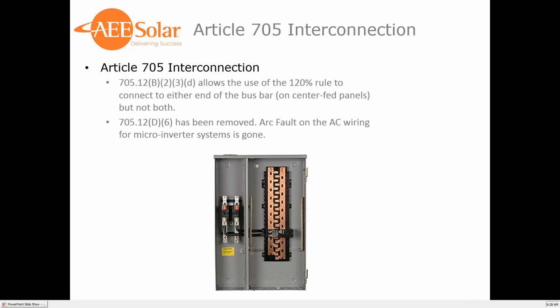So Article 705, interconnection. One of the biggest changes is to center-fed panels. 705.12B23D allows the use of the 120% rule to connect to either end of the bus bar on center-fed panels, but not both. There actually has been a TIA that's submitted for this. So if a state does not adopt the NEC 2017 code with this updated article for center-fed panels, the TIA is in place for adoption for AHJs that have not adopted the 2017 code. It's TIA 14-12, center-fed panels in dwellings.